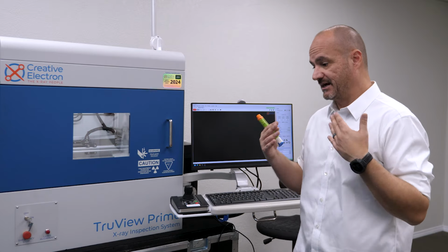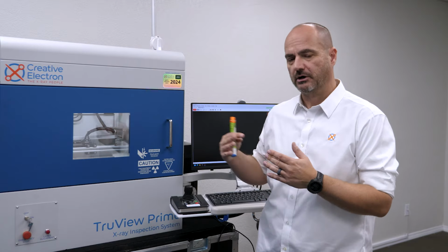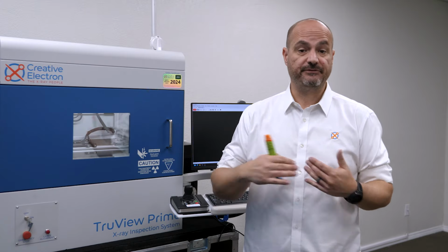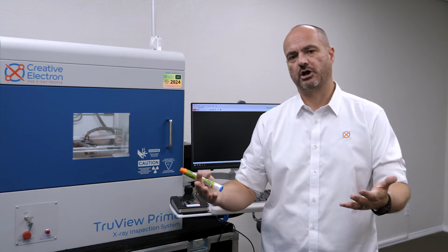The third stage we engage with medical device companies, the least fun stage, is when they have a recall, right? So that's when those companies are really under a lot of stress. Product has been discovered to be defective in the field. Things are coming back, maybe the FDA is involved, and now they have to X-ray inspect, they have to up their quality process. We get involved then to help them make sure that whatever happened never happens again, right? And we give them the traceability, the multiple check assurances so it won't happen again, and that whatever caused the problem is fixed, and those companies can show the FDA, for example, that the new process to manufacture the product fixes whatever has caused issue in the past.